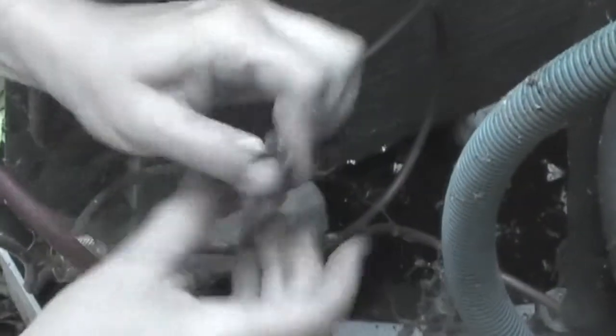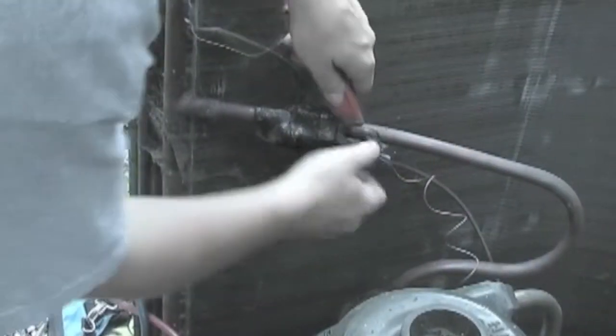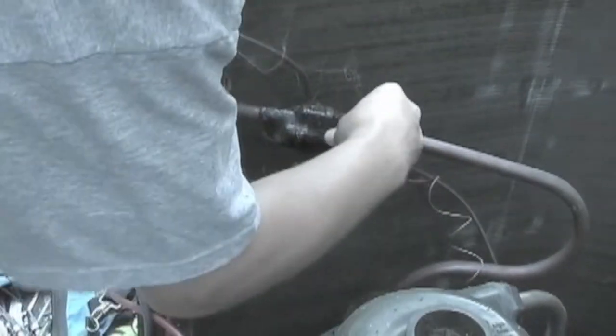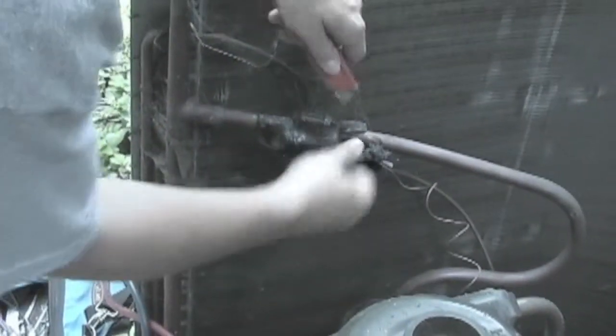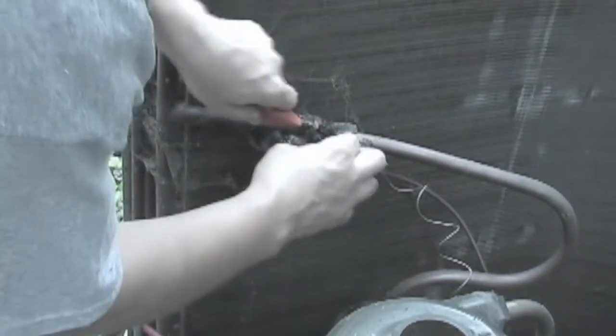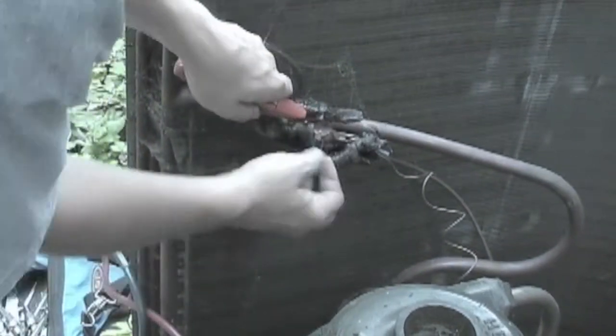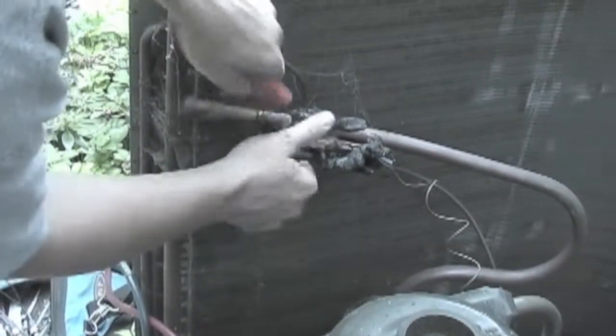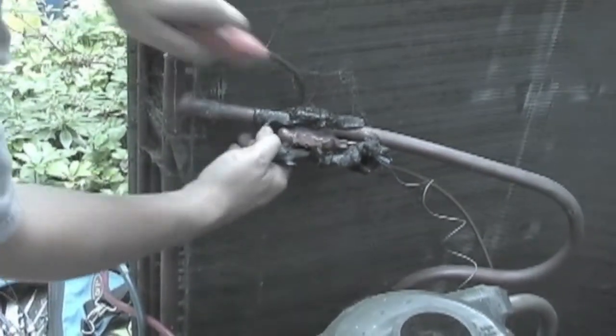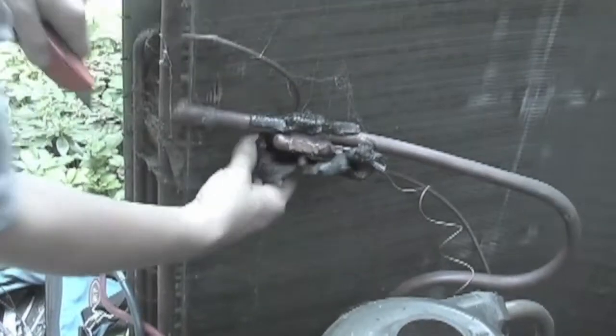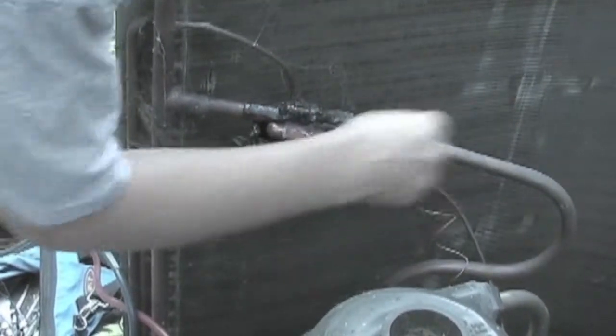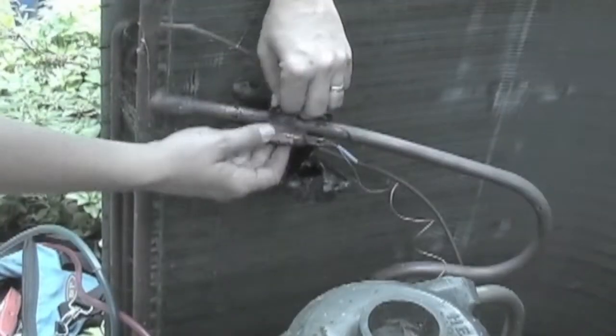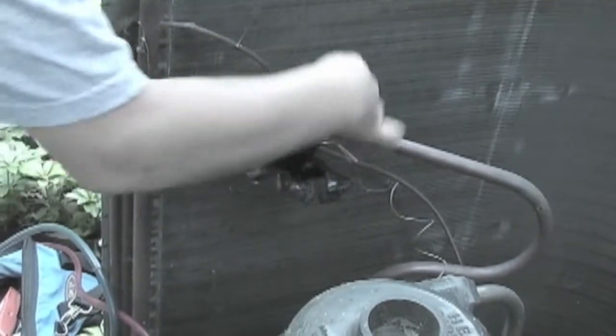Remove the high pressure switch if it's going to be reused on the new compressor. You need to remove the cork tape and TXV bulb from the main suction line. Cut and peel the cork tape back from the clamp, and use a flat head screwdriver to loosen and release the TXV bulb.